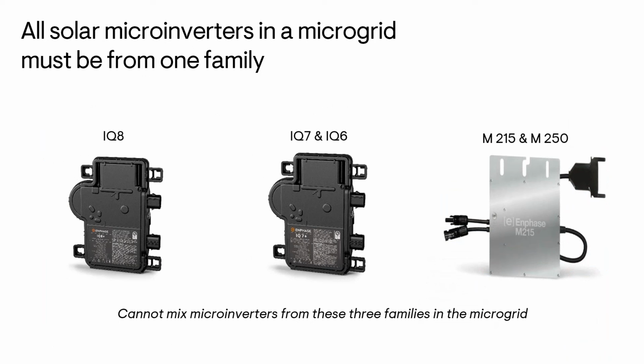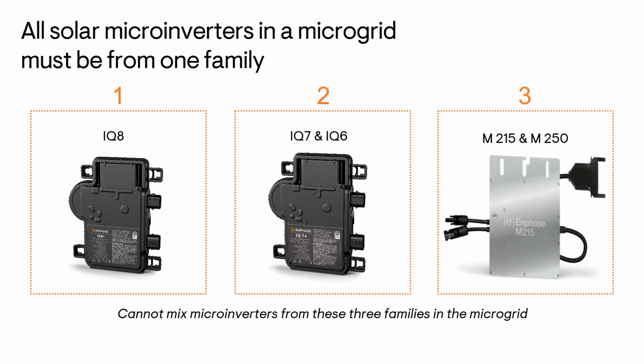In an Enphase Energy System microgrid, all microinverters on the solar array must be from the same family. And those families are highlighted here. In other words, microinverters from the IQ8 family can't be mixed with IQ7s or IQ6s in the same microgrid on the solar array. So sometimes we get asked by customers who already have an IQ7 system, why can't they just add a few IQ8s to their system and have a sunlight backup system? The reason is it's just not going to be a stable microgrid, because of the very different ways that the IQ7 and IQ8s behave and how quickly they react to changes in power demand and things like that. So it's important to be very clear with customers when that question comes up. You can't add IQ8s to an IQ7 system for a backup power configuration.